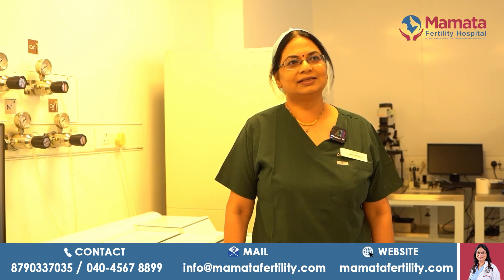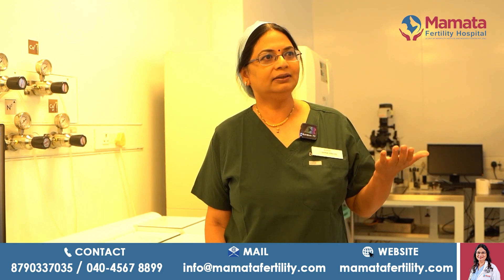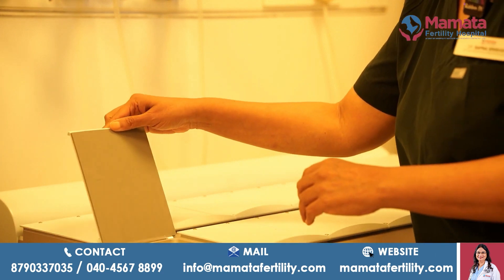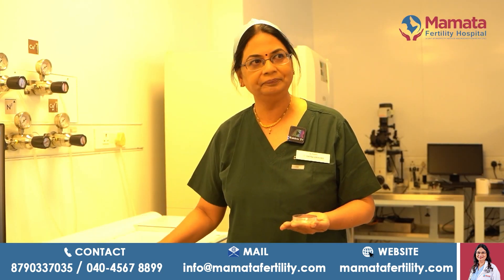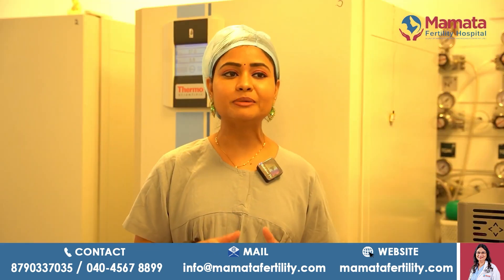Are there different kinds of incubators? Yes. Around the late 2000s, a purpose-built incubator was made specifically for IVF. We saw there were so many flaws in the big box incubator — the culture conditions were unstable. This bench-top incubator has a small chamber, and the same culture dish is individually placed in a smaller chamber. It is very easy for the culture conditions to recover faster. If the big incubator takes about 30 minutes to recover, this small bench-top chamber takes only about two minutes, making it far more superior for IVF culture.